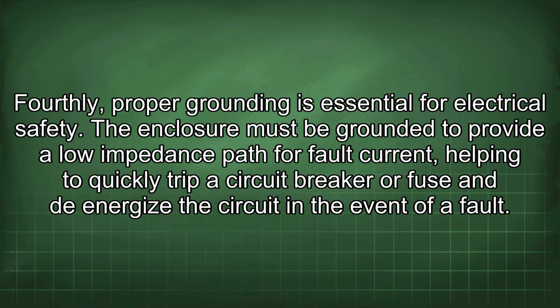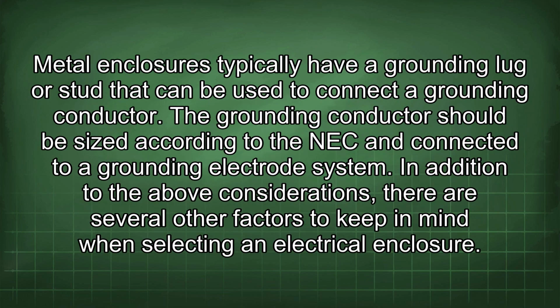Fourthly, proper grounding is essential for electrical safety. The enclosure must be grounded to provide a low impedance path for fault current, helping to quickly trip a circuit breaker or fuse and to de-energize the circuit in the event of a fault. Metal enclosures typically have a grounding lug or stud that can be used to connect a grounding conductor. The grounding conductor should be sized according to the NEC and connected to a grounding electrode system.